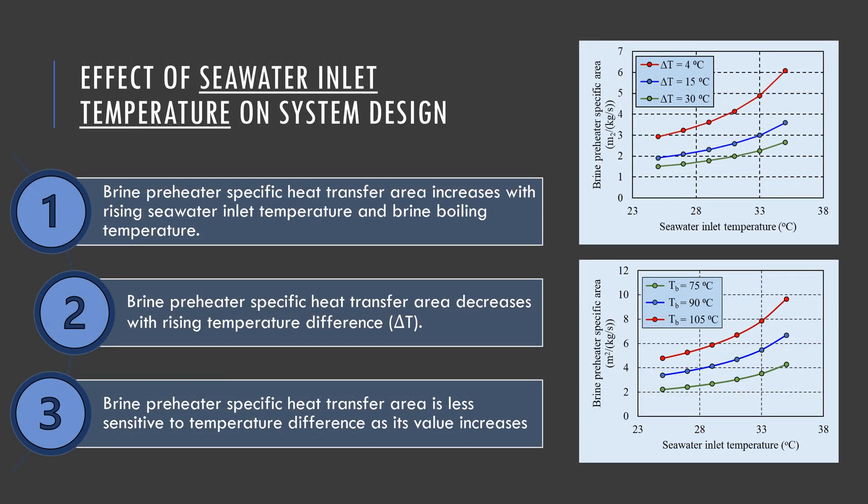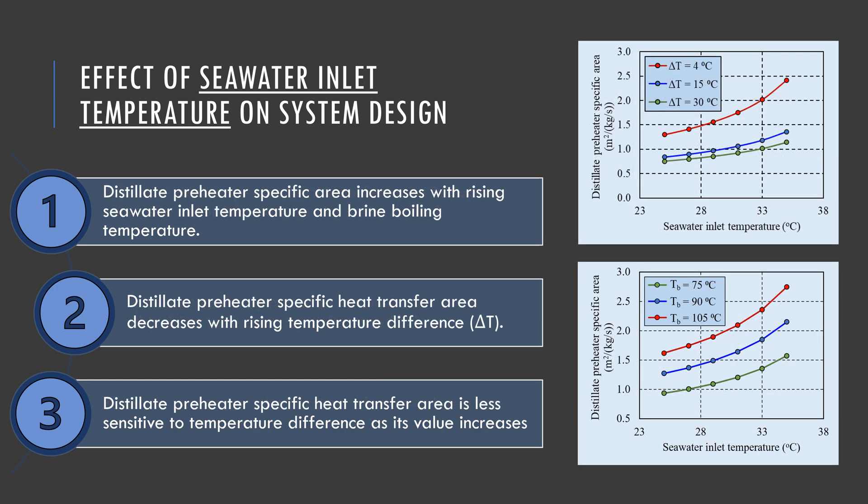Another important factor is the seawater inlet temperature, which affects the brine preheater specific area by increasing it as the seawater inlet temperature increases. However, the specific area decreases with rising temperature lift across the compressor, but increases with rising brine boiling temperature. These outcomes result from the changing mean temperature difference in the preheater affecting its size. For the distillate preheater, its specific area increases with seawater inlet temperature and brine boiling temperature, whereas it decreases with rising temperature lift across the compressor — similarly due to the changing mean temperature difference in the distillate preheater.